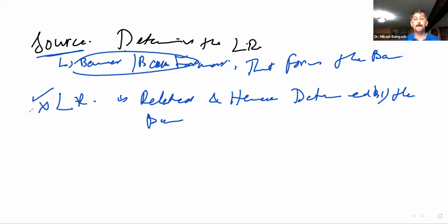Can you repeat that one for me? It's all going to be dependent upon how your beam looks, or we like to say the measurements of your beam, that will determine whether you have a good lateral resolution or a bad lateral resolution.